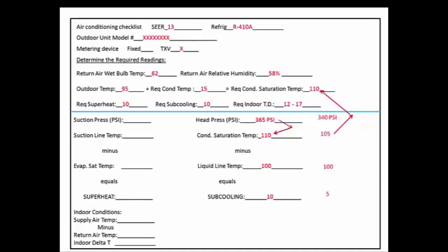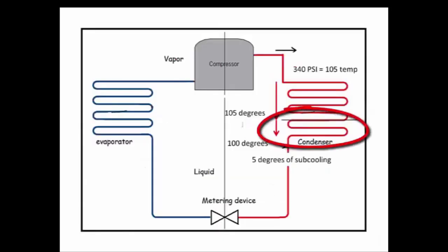Well we know a couple of things here. We know that our head pressure is low. Up above, the required condenser saturation temperature should be 110, but it's actually 105. And since the condenser saturation temperature is low, head pressure is low as well. So that's indication number one. Indication number two is we have low subcooling. We only have 5 degrees of subcooling and we should have 10. Those two things are going to tell us that we have a low level of refrigerant in our condenser.